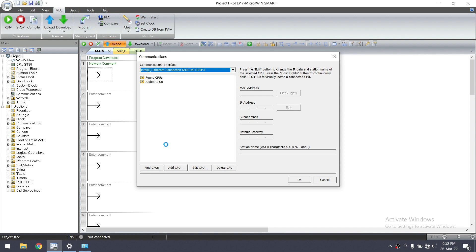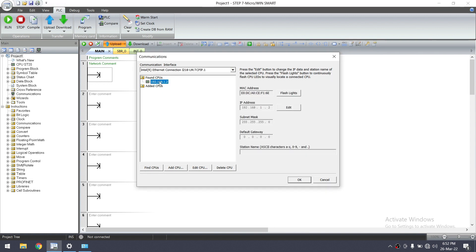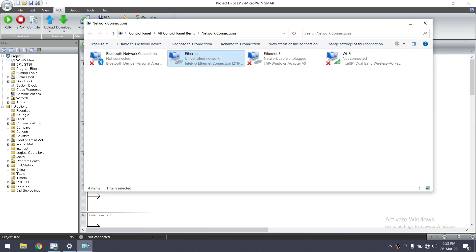It will check for any PLC on the network and display it here. It shows one PLC found — the PLC IP address is 192.168.1.2. This means the PLC is in the 192.168.1 series, so we need to have our laptop IP address in the same series. Let's change the IP address.